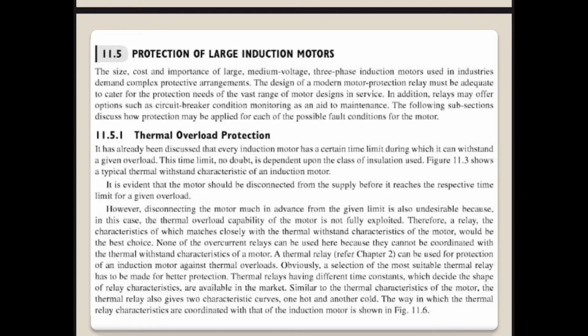We have already discussed that every induction motor has a certain time limit during which it can withstand a given overload. Before it gets heated up to the thermal handling capability of its insulation, there is some time. So before the motor reaches the highest temperature the insulation can withstand, it has to be isolated from the power supply, and to do this we have to use relays.